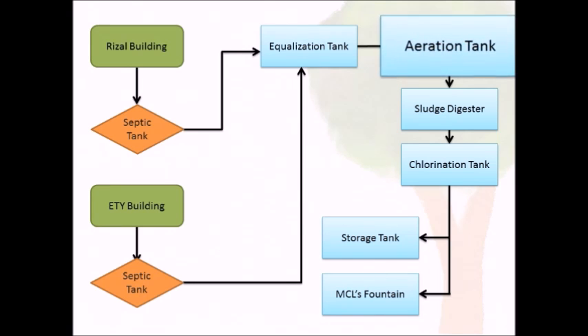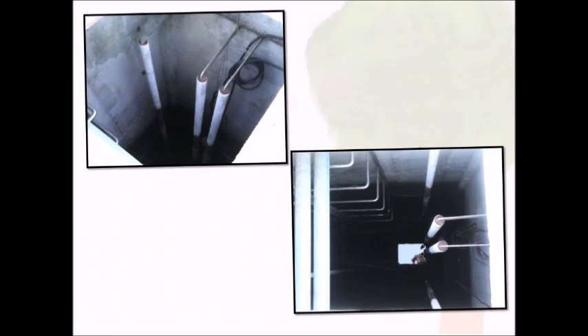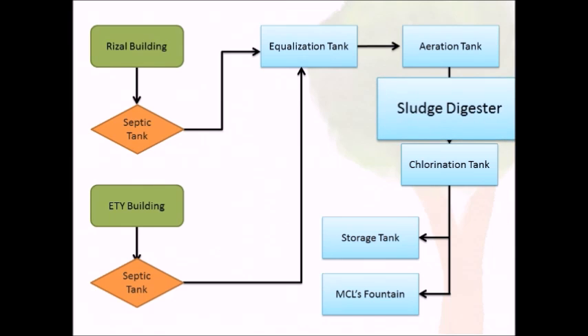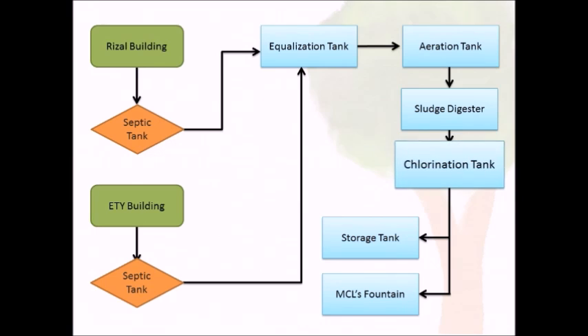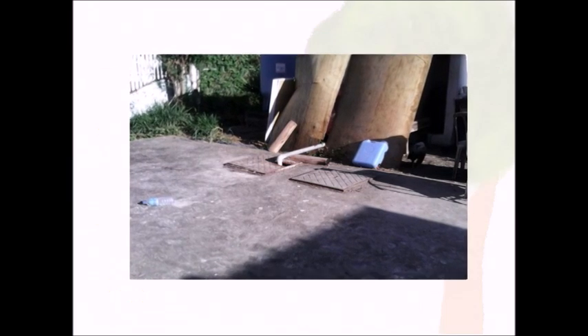After the equalization tank it will go to the aeration tank, where the water treatment is done by a network of tube-type fine bubble diffusers. The sludge digester tank allows the sludge to settle to the bottom so that water will be separated from it. The chlorination tank will treat the water that came from the settlement tank, to disinfect it and make it ready for storage or disposal.